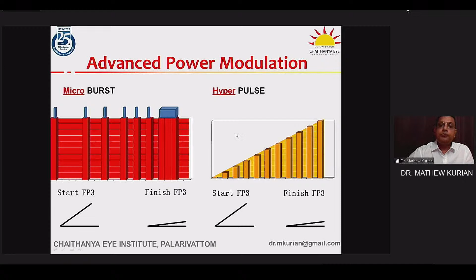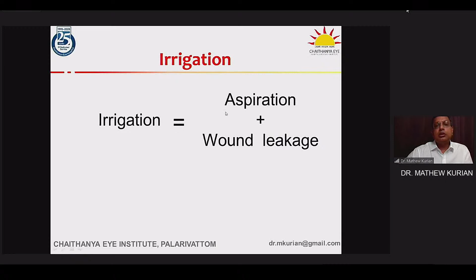Next, we go on to the second half of the talk, which is on fluidics or irrigation. With the irrigation, we want to balance the aspiration that happens at the phaco tip plus anything that is leaking from the wound. In conventional machines, it was bottle height in the gravity-fed machines, and we were able to manage between 65 to 150 centimeters of bottle height, depending on the machine and what is permitted by the roof of the operation theater. Today, with active fluidics, we can give a much more precise intraocular pressure control inside the eye.